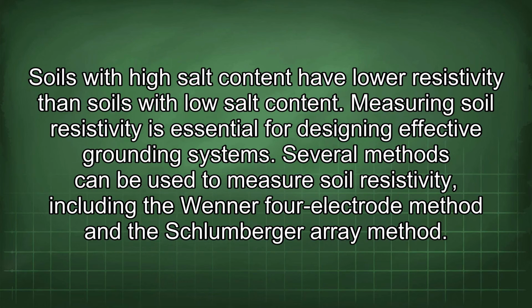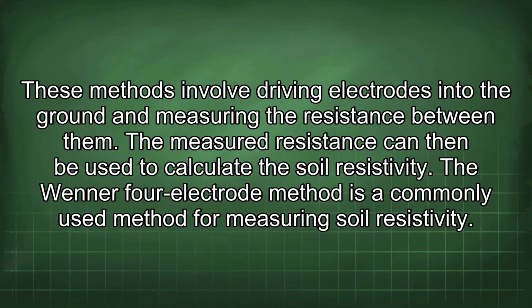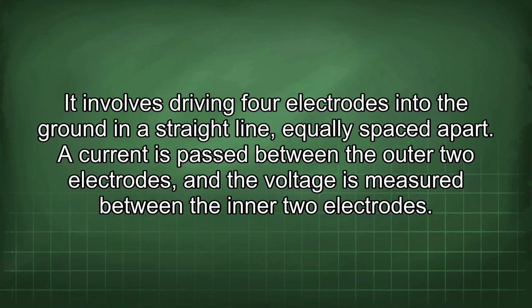Several methods can be used to measure soil resistivity, including the Wenner 4-electrode method and the Schlumberger array method. These methods involve driving electrodes into the ground and measuring the resistance between them. The measured resistance can then be used to calculate the soil resistivity. The Wenner 4-electrode method is a commonly used method for measuring soil resistivity. It involves driving 4 electrodes into the ground in a straight line, equally spaced apart. A current is passed between the outer 2 electrodes, and the voltage is measured between the inner 2 electrodes.